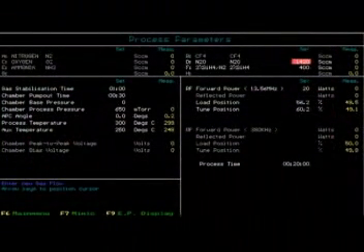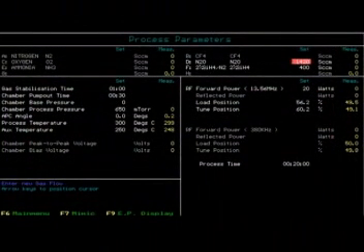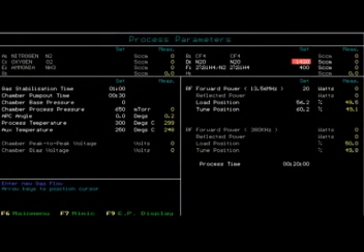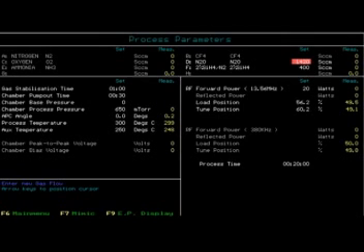There are two numbers that should be monitored during deposition: the reflected power and the chamber bias voltage. The tuning network will automatically adjust the load and capacitor positions to reduce any reflected power — this number should be close to zero. Chamber bias voltage affects film quality as well as the deposition rate and should remain near constant with the same recipe throughout the process. If the number varies, this indicates a change in the chamber condition, and MRC staff should be notified.